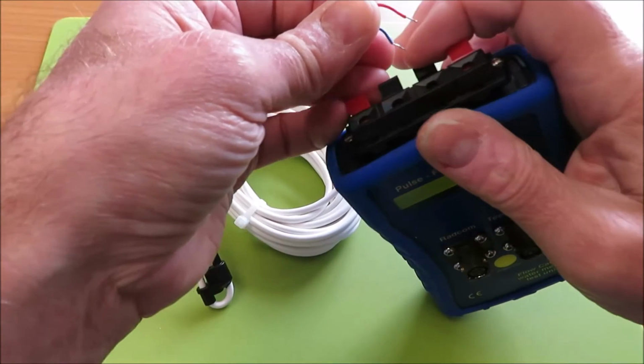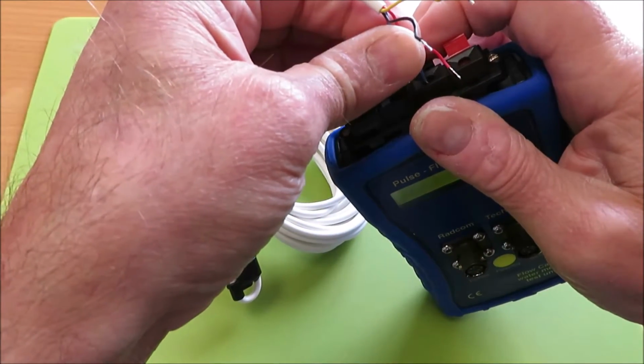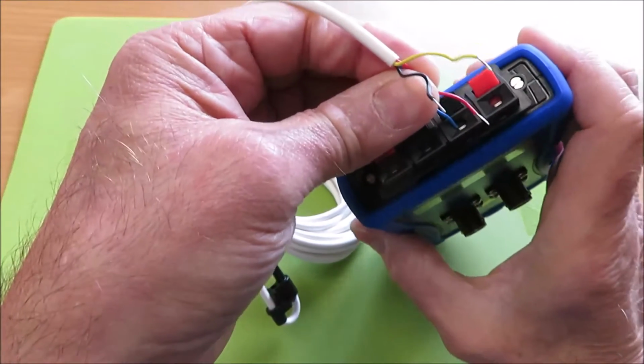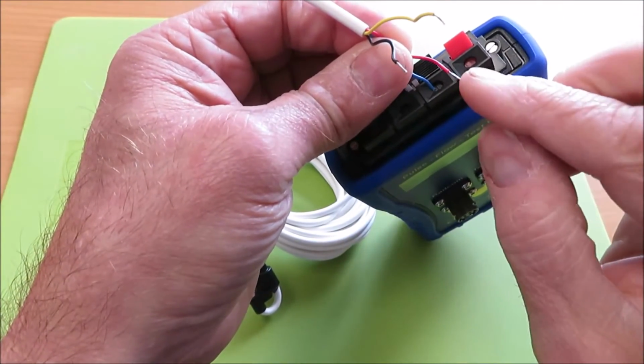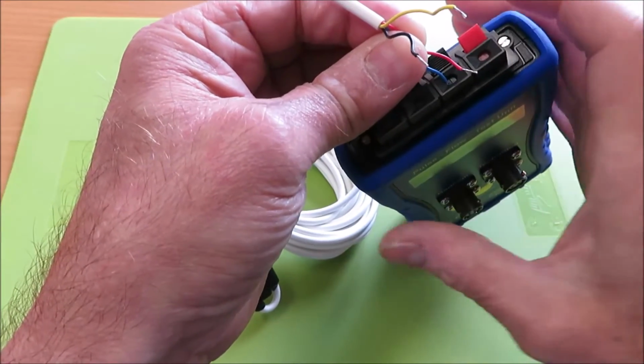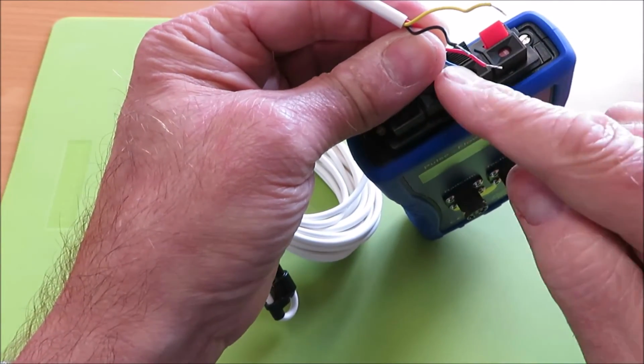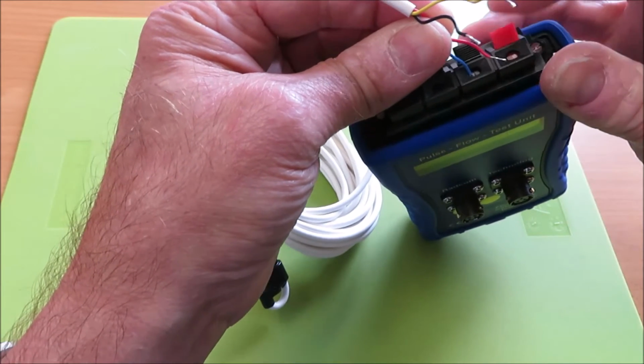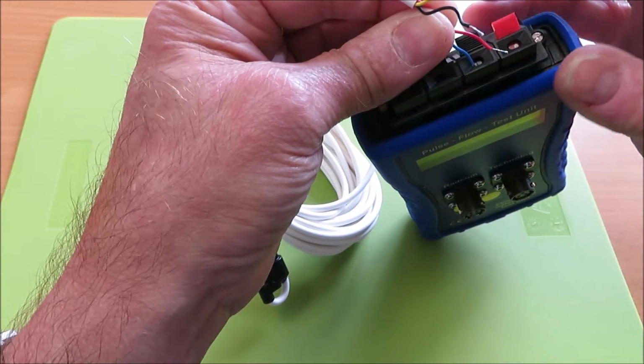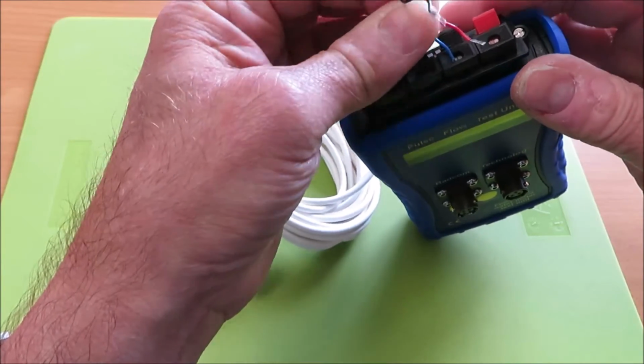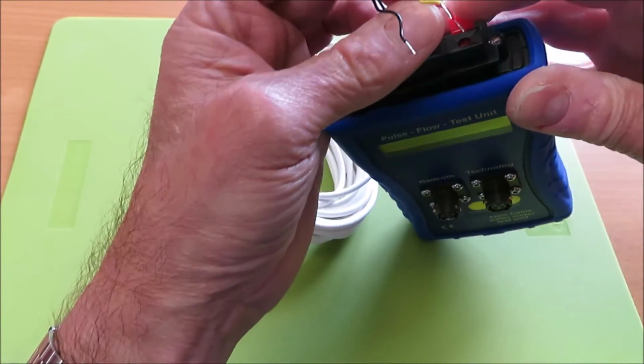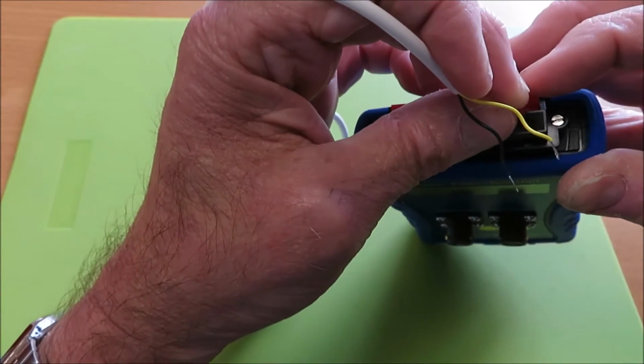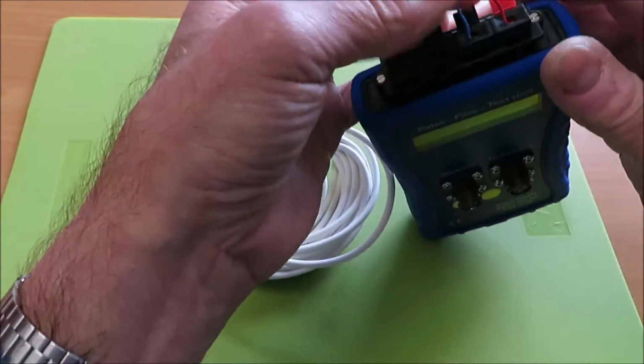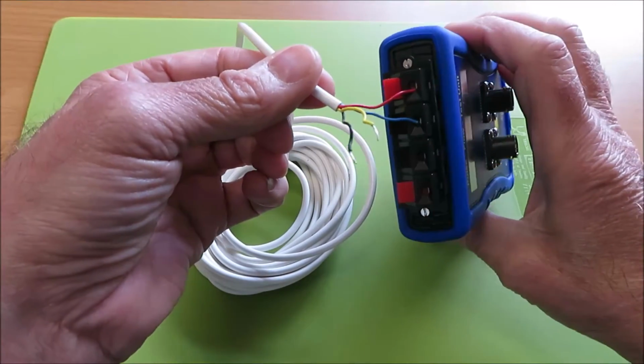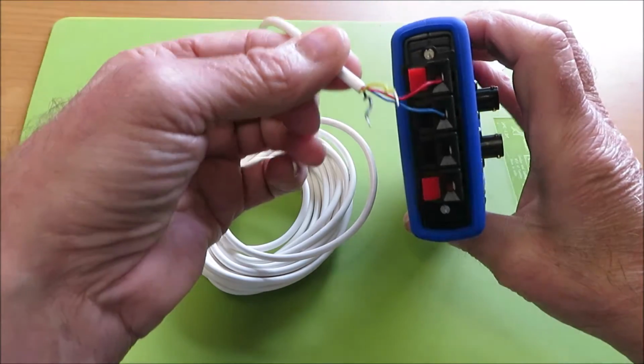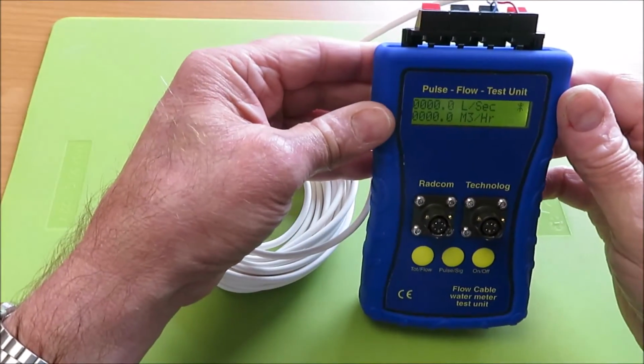So what I will do is I'll insert the blue into the black, and you'll notice that I'm being very careful to make sure that it goes onto the metal conductor, not the sleeving. It is possible to trap the connector onto the insulated sleeving and not the conductor, and if you do that you won't get a reading.